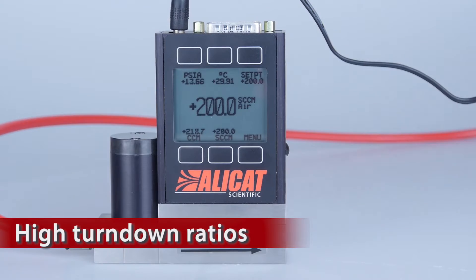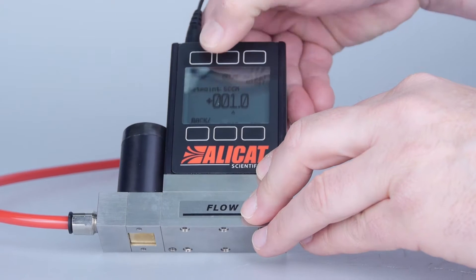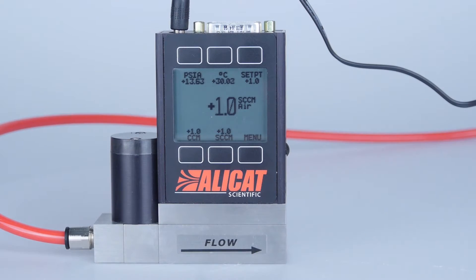Alicat mass flow controllers maintain their accuracy down to half a percent of full scale — a turn-down ratio of 200 to 1. Many mass flow controllers offer a turn-down ratio of only 50 to 1.